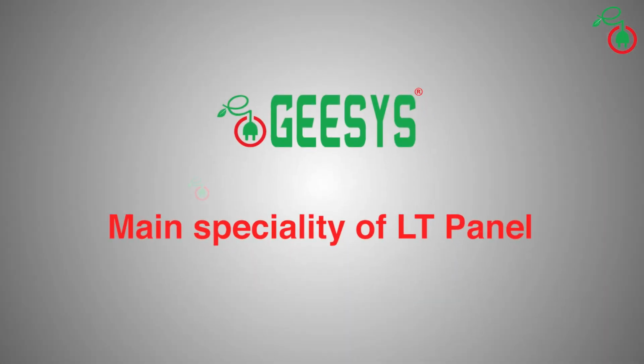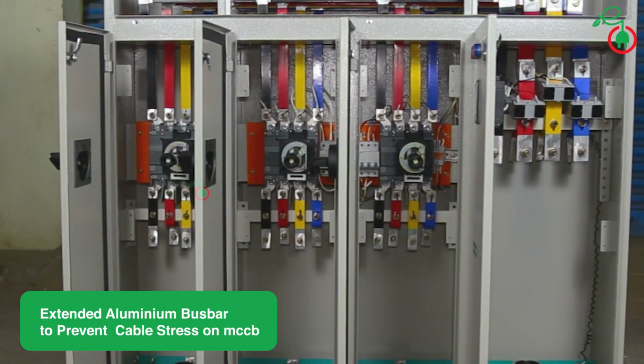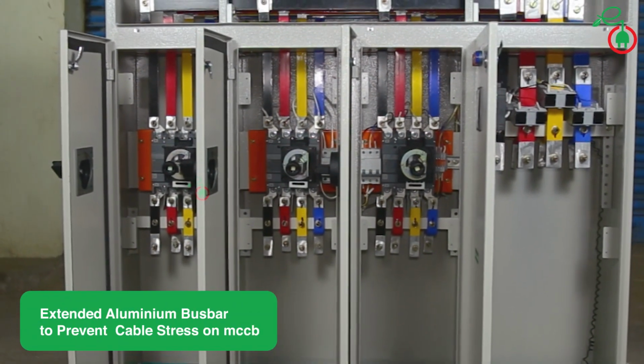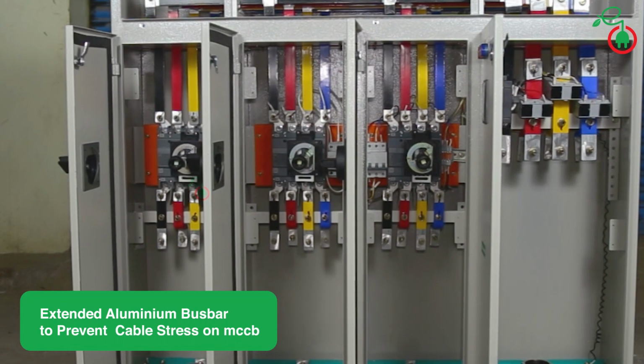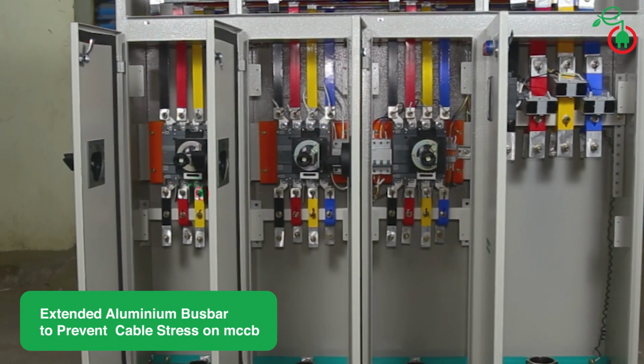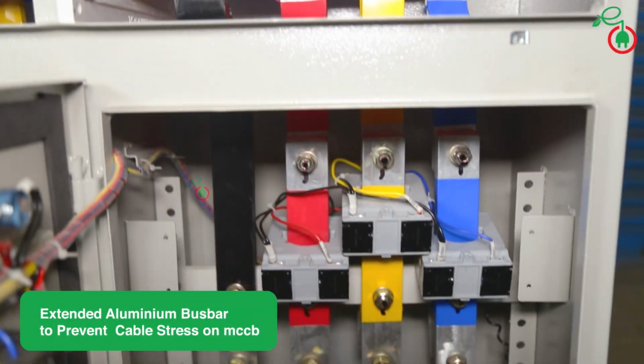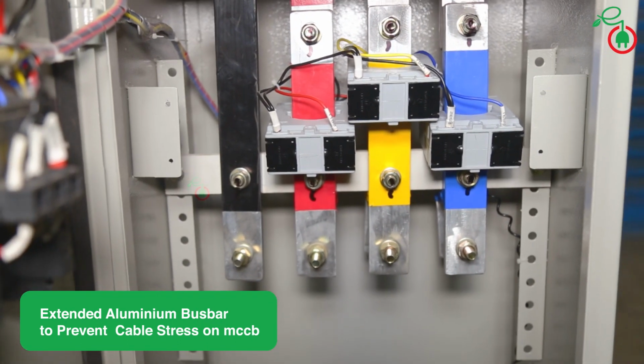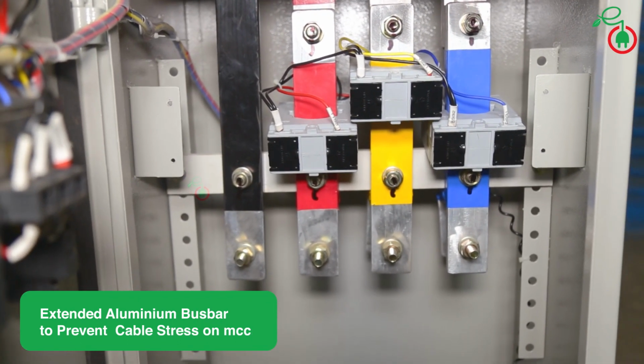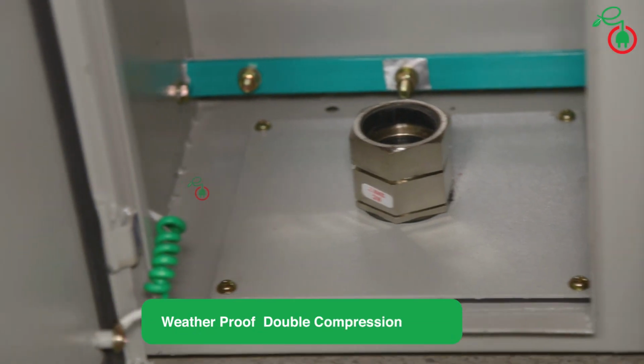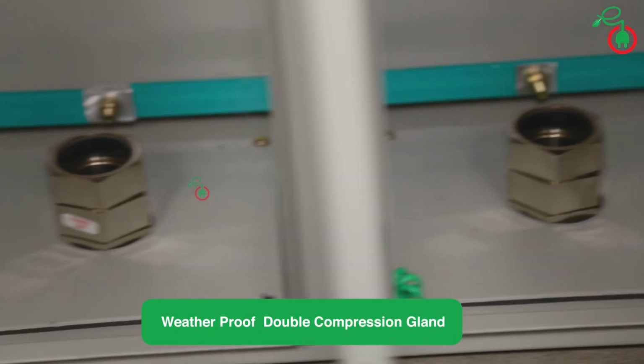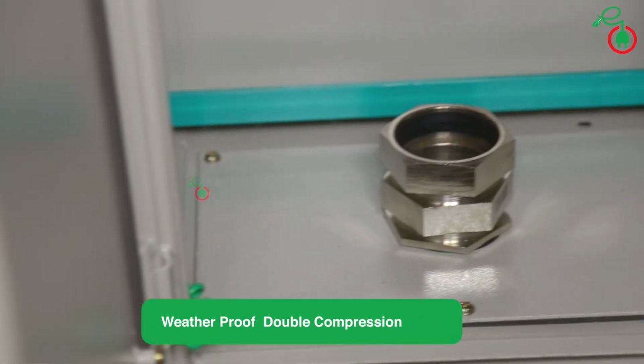The main specialty of GEESYS solar LT panels is that the MCCB spreader terminals are extended with the help of aluminium busbar to terminate the cable on the MCCB. Since we connect the inverter cable through an extended busbar to the MCCB, the MCCB will not get strained. We have provided weatherproof double compression glands at the input as well as the output.